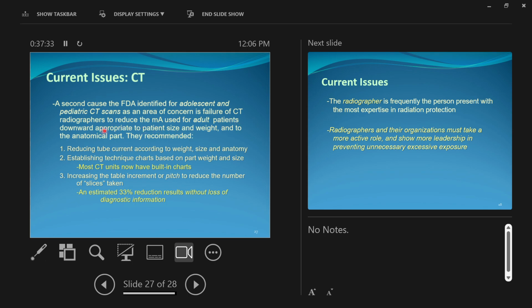So instead of adjusting downward for patient size and weight and the anatomic part, the recommendation for CT radiographers is to reduce the x-ray tube's current according to weight, size, and anatomy, and establish technique charts like we have in our regular x-ray rooms based on part, weight, and size. Most are built into the machines. Increase the table increment or pitch to reduce the number of slices taken.